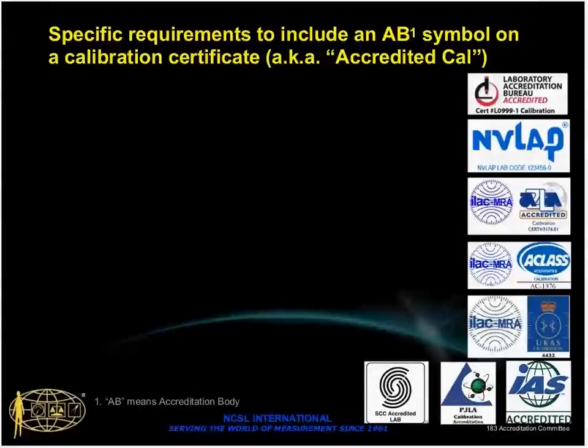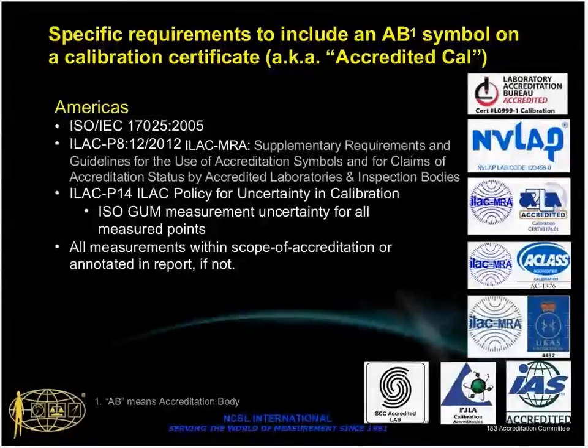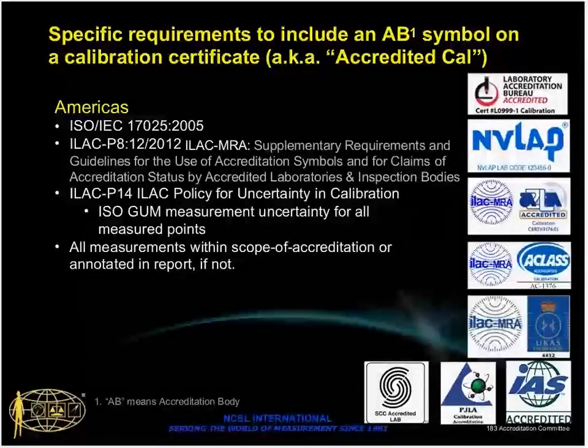But looking at the requirements that go into this, it's quite detailed. When we look at what we have in the Americas, there are several different things that go into this. First of all, we have the requirements of 17025. This is the standard that we're being assessed to, and what the accreditation body is providing the accreditation on. But as part of that, we've also got the ILAC document P8. This is a document that accreditation bodies have to follow when laboratories are using their symbol, and inside P8 it describes when we use the symbol on the certificates, calibration labels, advertising and publicity, et cetera.